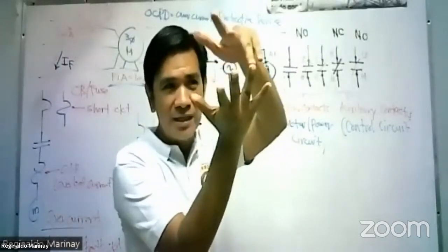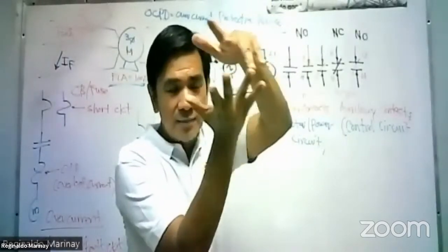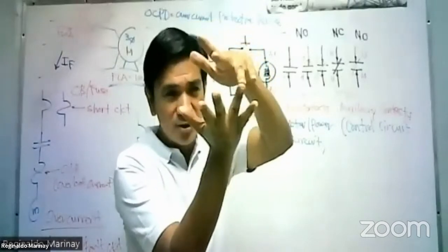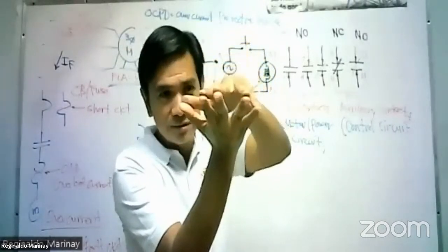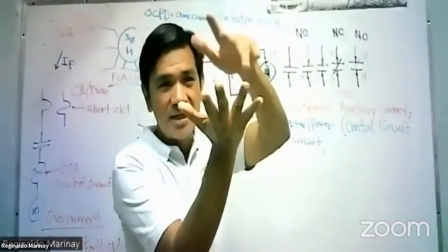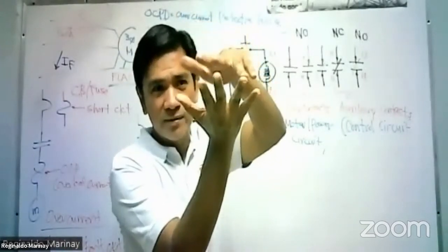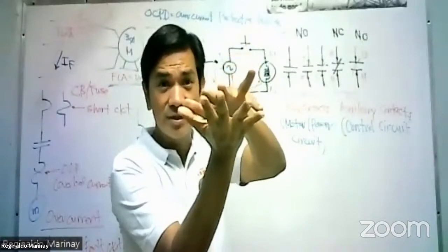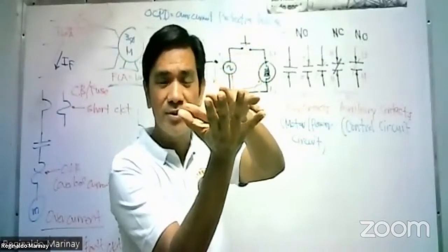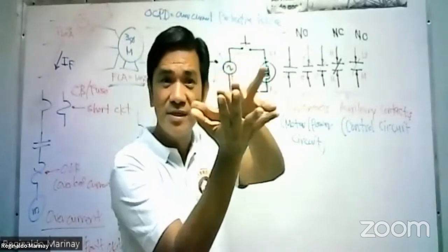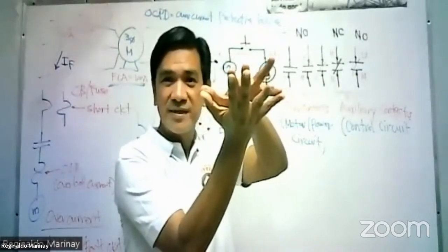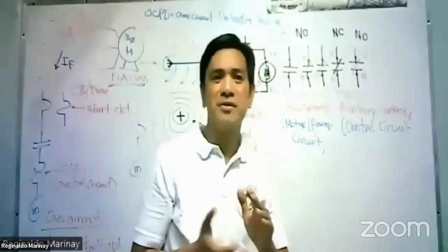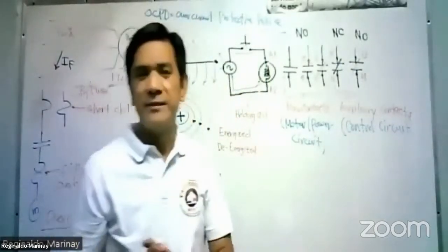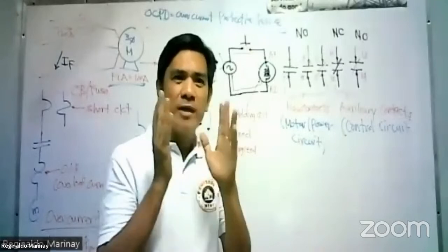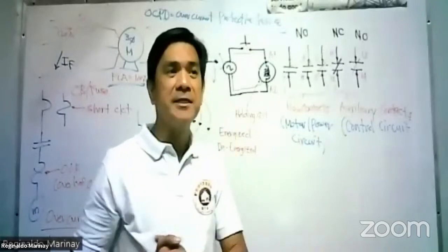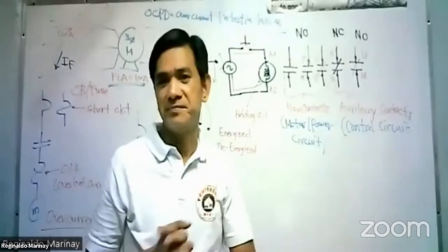Take it slowly but surely. If the holding coil becomes energized, you will see this action. See? What happened to all the normally open contacts? They become closed, right? But what happened to the normally closed contact? It becomes open, right? That is the heart of the operation of a magnetic contactor. That is one of the most important ideas in interpreting motor control systems.